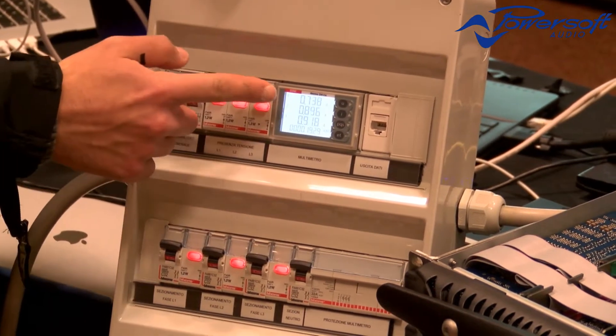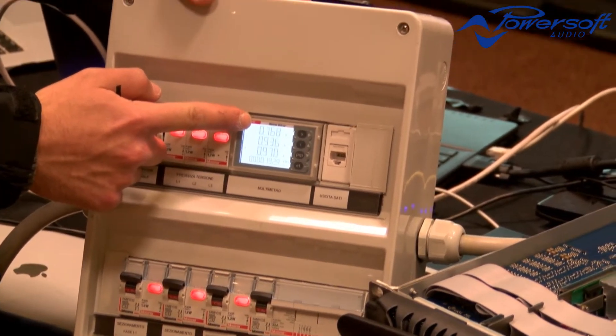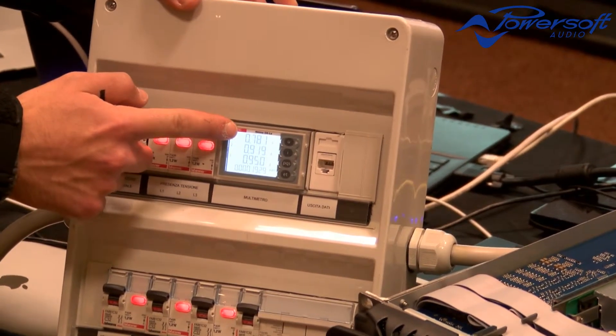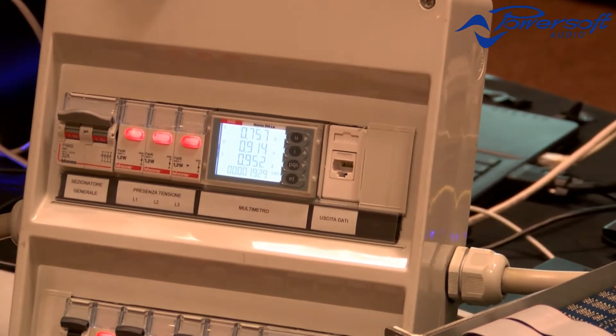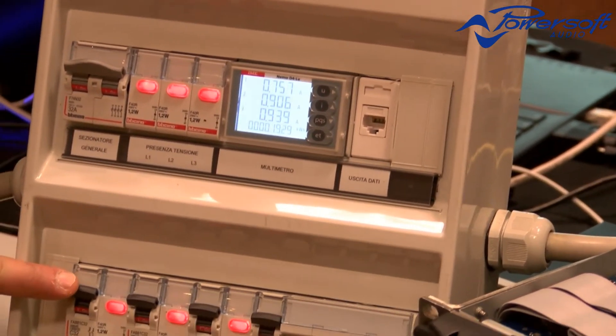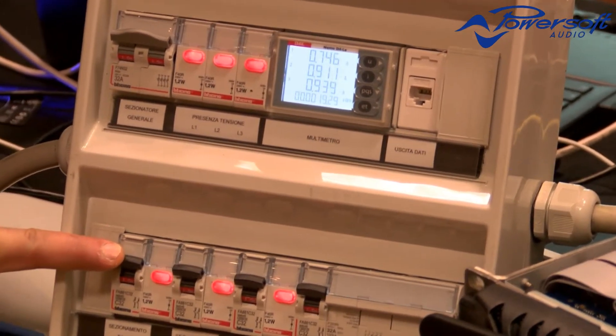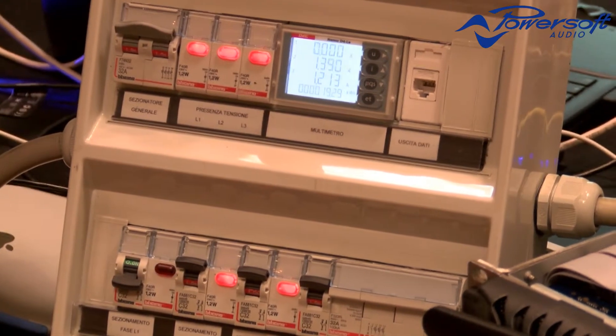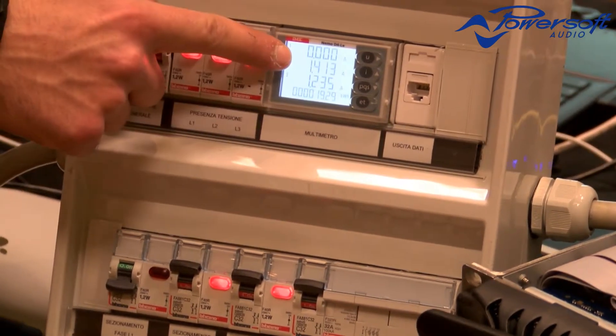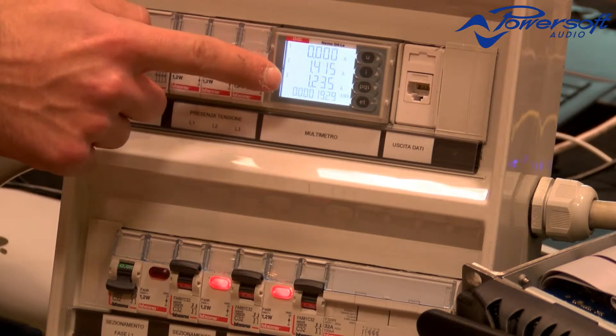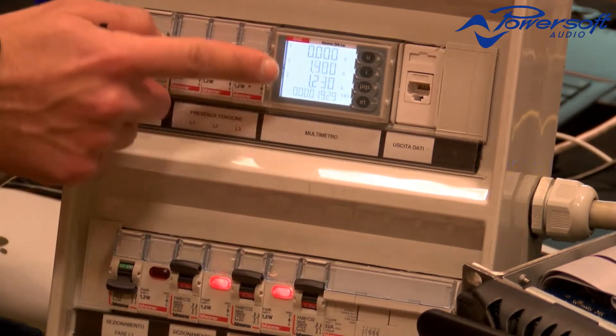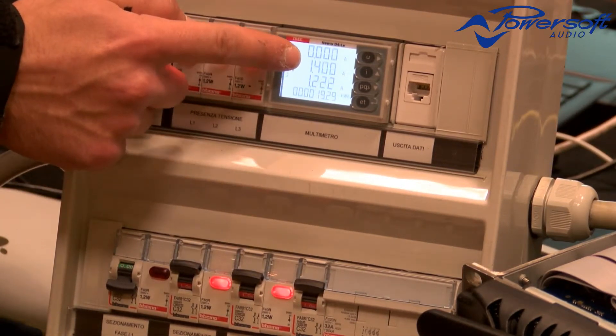If I cut one phase - phase one for example - the amplifier now spreads the load across the two remaining phases. We are reading 1.3 amps more or less on phase two and phase three.